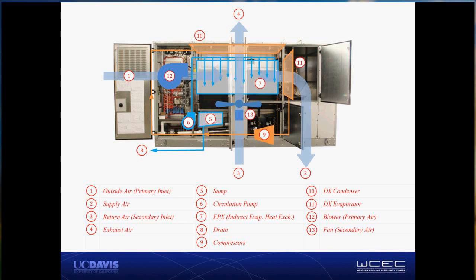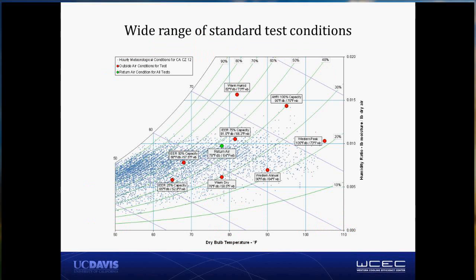Our laboratory tests did a really good job of mapping the performance using return air conditions and also outside air conditions over a variety of airflow rates and across a whole range of psychrometric points. Here's what our design of experiments looked like. We tried very carefully to map a broad range of space. This is actually the same design of experiments that we're using for all of our laboratory tests of this type of equipment now.